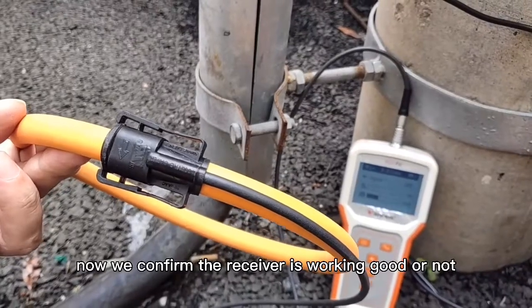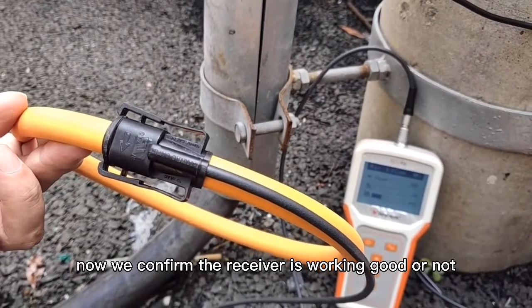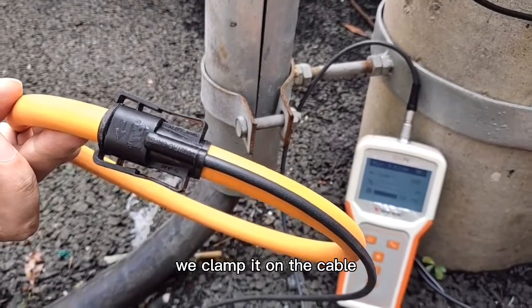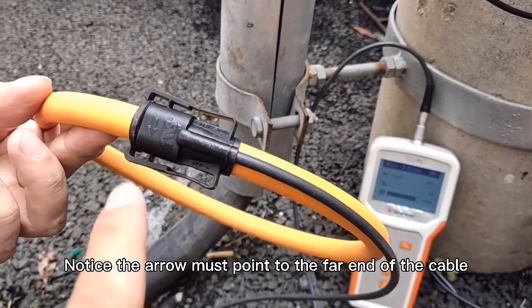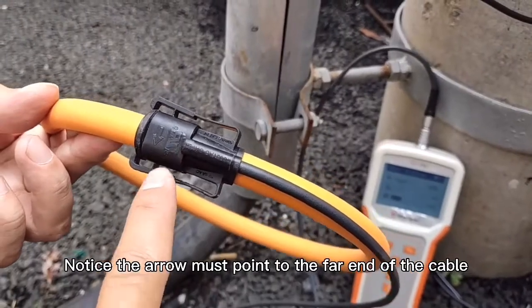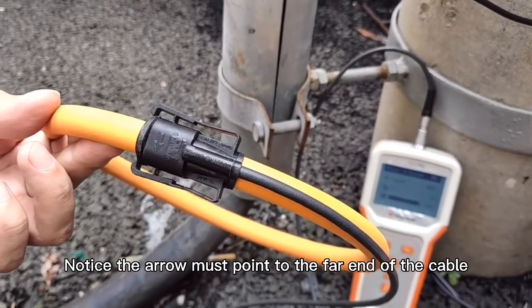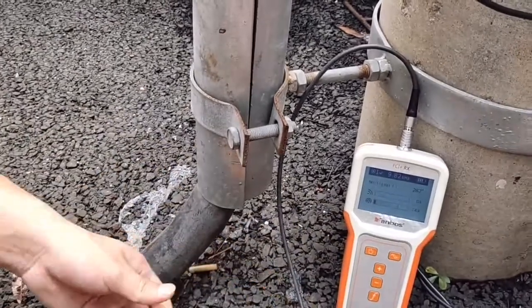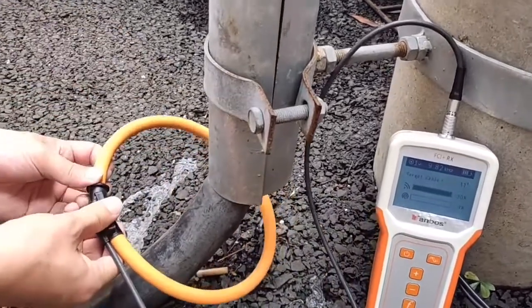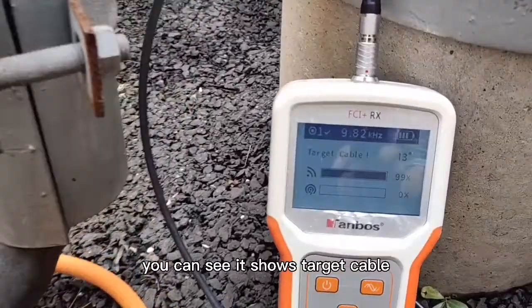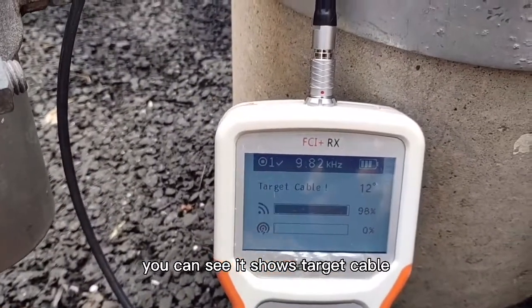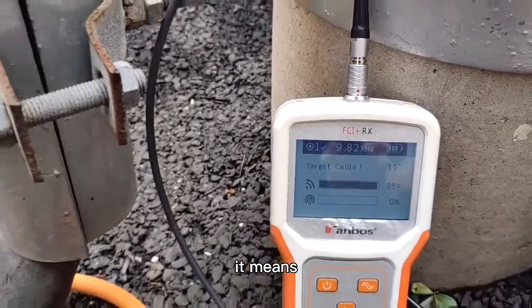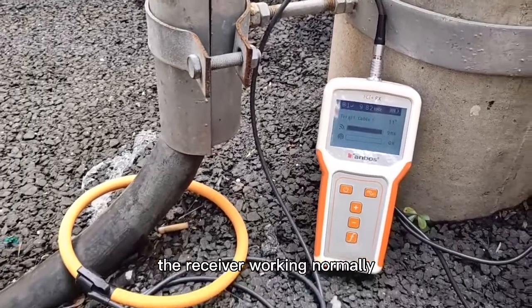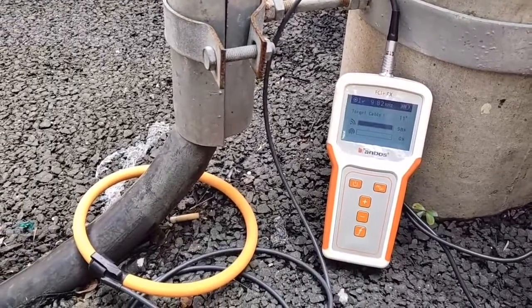Now we confirm the receiver is working good or not. We clamp it on the cable. Notice the arrow must point to the far end of the cable. You can see it shows target cable. It means the receiver working normally.